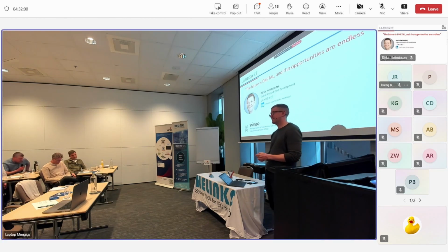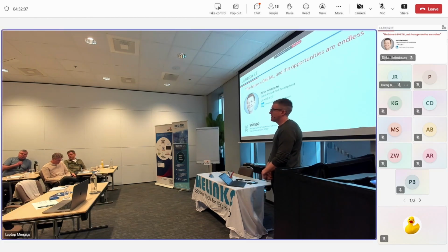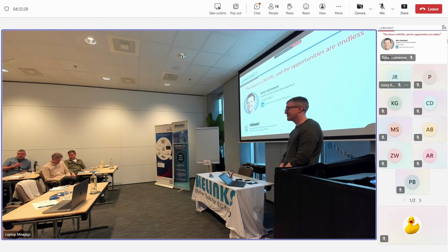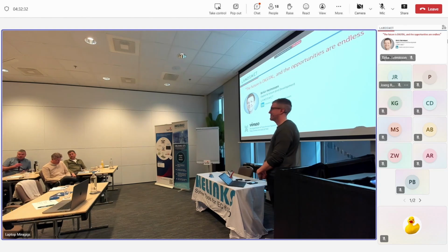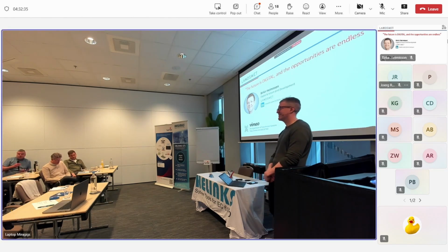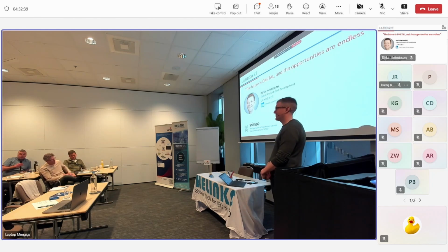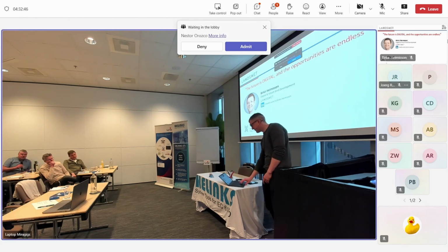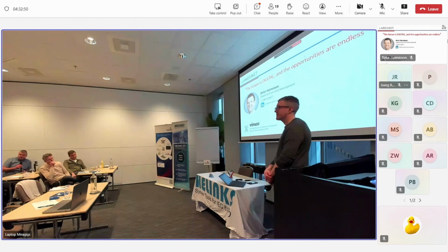Just to follow up on the question about redundancy: we found the same as you did. We tried the redundant route, and it got to the point where you were adding extra engineering to overcome a problem that was probably unlikely to happen anyway. For example, how do you send one DNP3 address command to two 61850 endpoints? You need some logic in the middle to handle that, and likewise going back up. You might be able to do something in the HMI, but we found the control room top end was even more antiquated and couldn't send one point to two DNP3 addresses going the other way. So you end up with too much duplication trying to achieve redundancy, making it not worthwhile. I think 61850-90-20 is going to try to add some redundancy functionality into the standard.